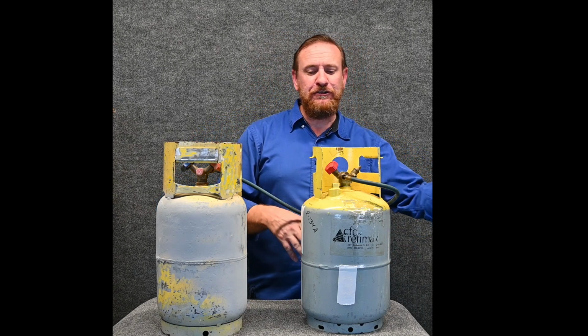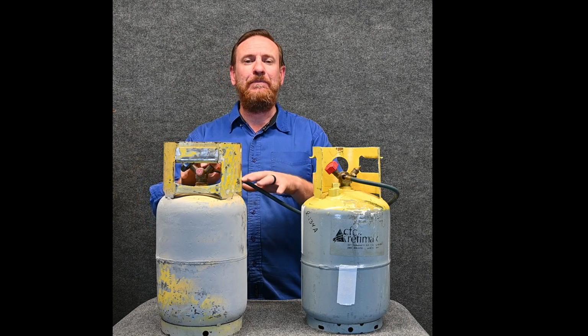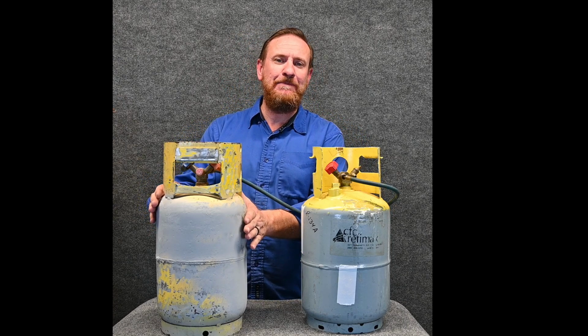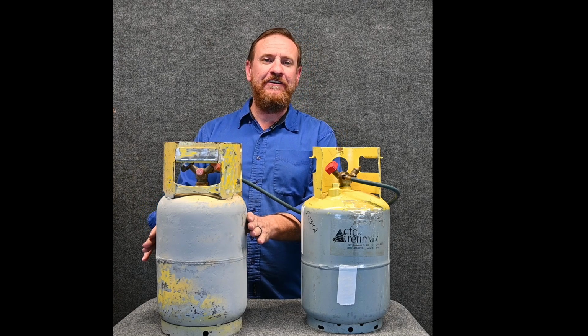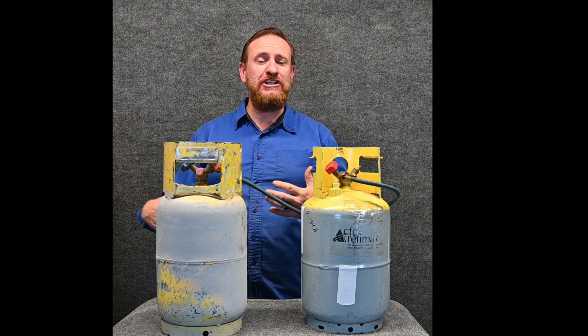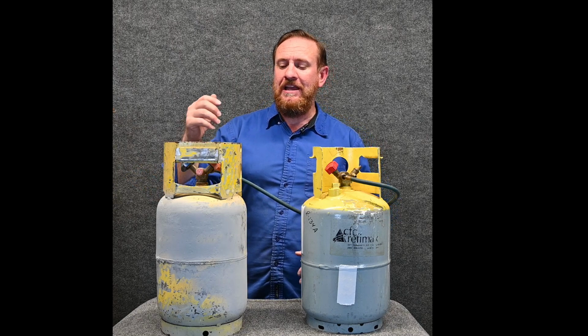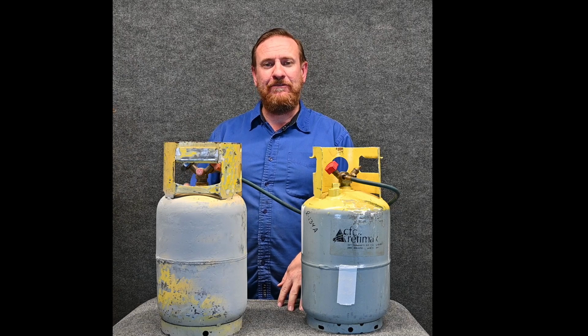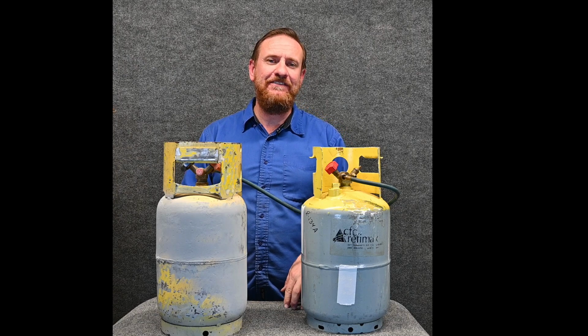So all the other refrigerant migrated into these two tanks that were completely full, which really panicked me, because this tank should never be over 80% full. If it's over 80% full, it could have an issue of expansion and it could rupture or explode. So it was kind of a big deal. I had to sit there and baby it to make sure I got the refrigerant out of that tank to make sure we didn't have a safety issue.